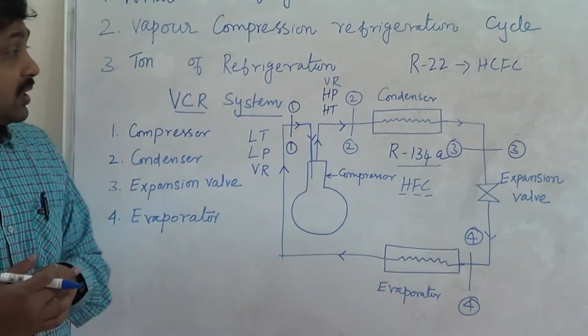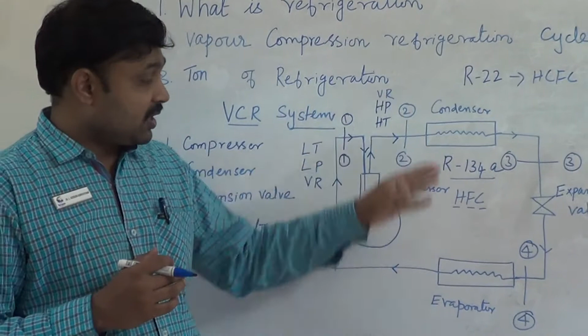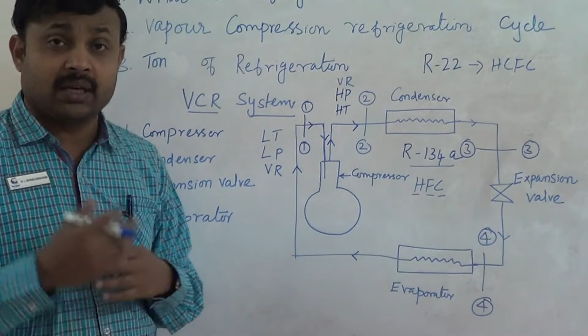Now at this condition, the refrigerant is made to flow through the condenser. We all know what condensation is. Condensation is the conversion of vapor into liquid. The opposite of condensation is evaporation or vaporization, the conversion of liquid into vapor. That takes place in the evaporator, and the conversion of vapor into liquid takes place in the condenser. Generally only latent heat transfer takes place. Latent heat means the phase change happens without change in temperature and pressure, theoretically speaking, but practically there will be a decrease in pressure and temperature as well.